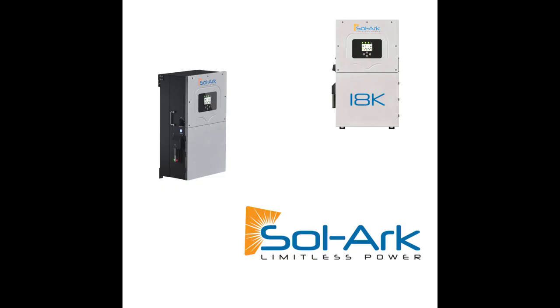Three separate isolated MPPTs in the Sol-Ark 18K. That means they are isolated from each other. So let's say you don't have the best configuration on a roof, it's not all flat or one direction facing. You can put similar strings on the same MPPT and then maybe a different facing string on MPPT 2 or 3, which will help with your production instead of derating the singular MPPT. Maximum strings in each MPPT is up to 2. You can and may want to go up to 3, but then that starts to inline or add inline fuses, which may make things complicated and add to the bill of materials of the projects. We recommend staying within 2.